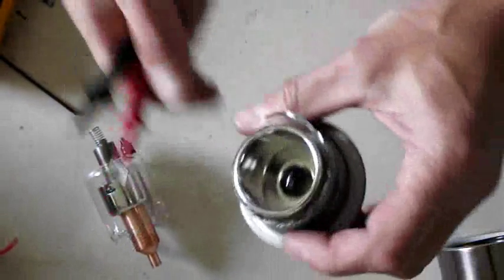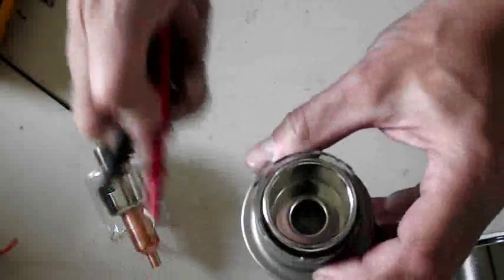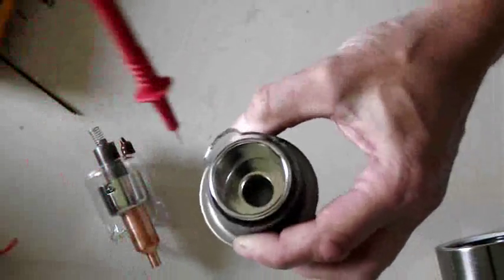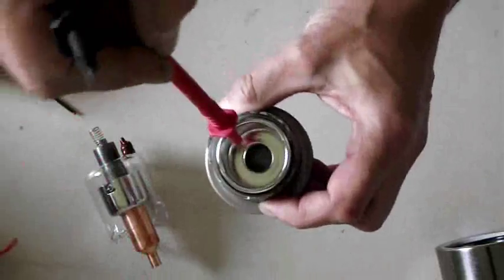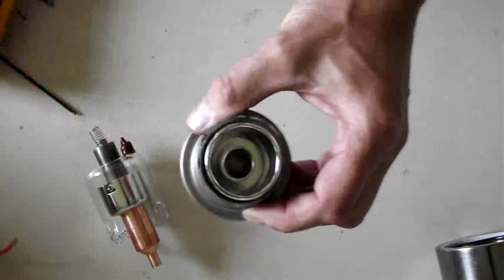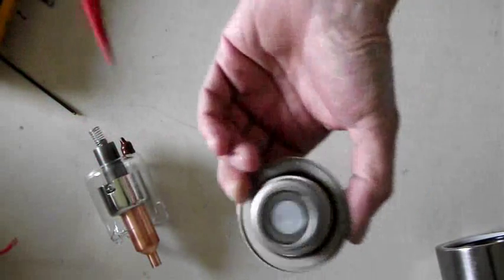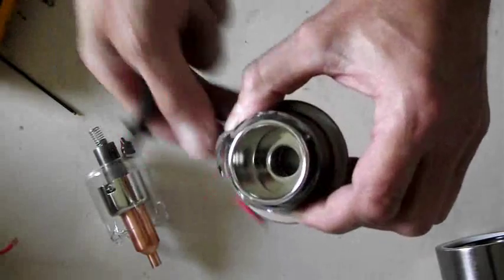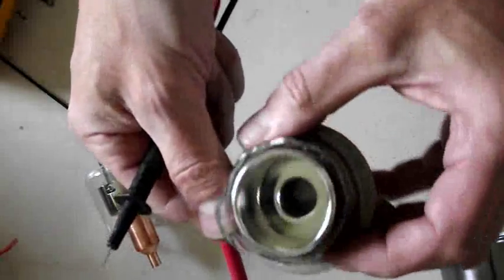So somewhere in here is still a heater. There is a little bit of strange marking on the beryllium window just on the inside from this dent here. So possibly that's where the vacuum failed.